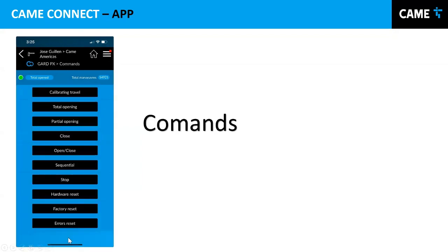You can go back here. You can do a calibration travel. So you're gonna send a calibration travel, like encoder calibration. You can do a remote encoder calibration. Once you do that, you should be able to see whether or not the problem has been gone.